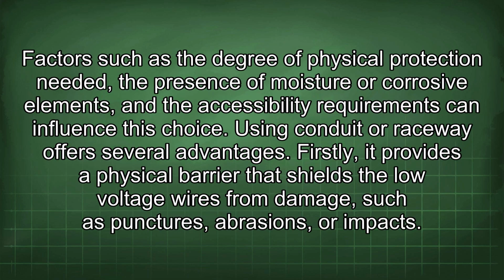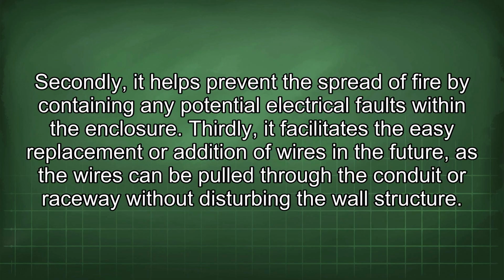Factors such as the degree of physical protection needed, the presence of moisture or corrosive elements, and the accessibility requirements can influence this choice. Using conduit or raceway offers several advantages. Firstly, it provides a physical barrier that shields the low-voltage wires from damage such as punctures, abrasions, or impacts. Secondly, it helps prevent the spread of fire by containing any potential electrical faults within the enclosure. Thirdly, it facilitates the easy replacement or addition of wires in the future, as the wires can be pulled through the conduit or raceway without disturbing the wall structure.